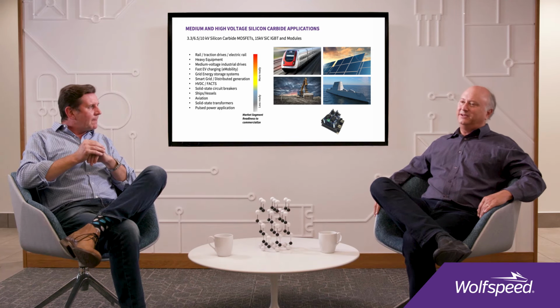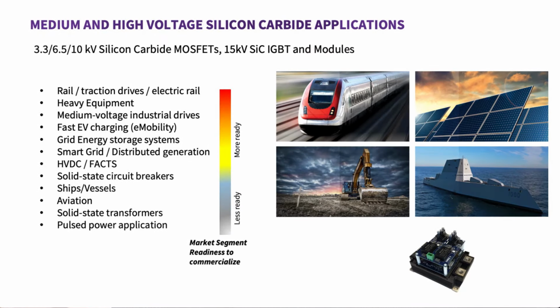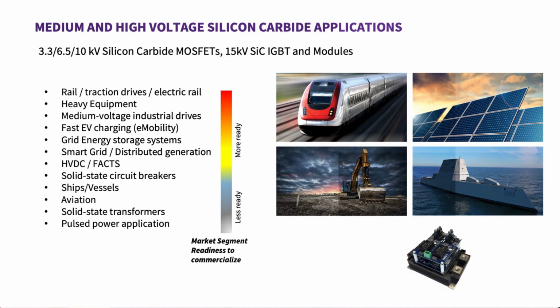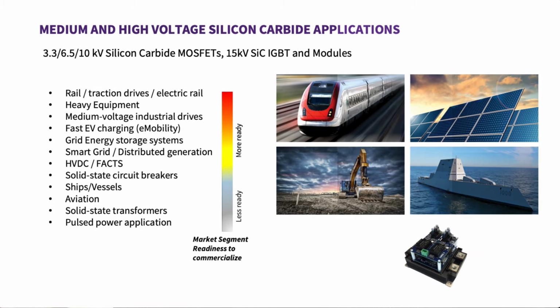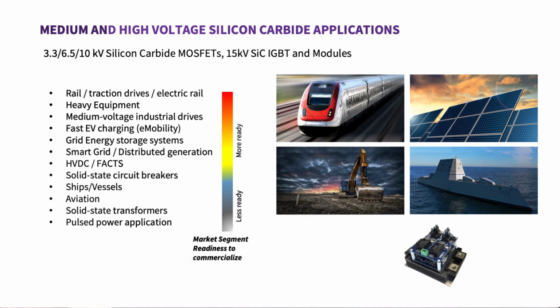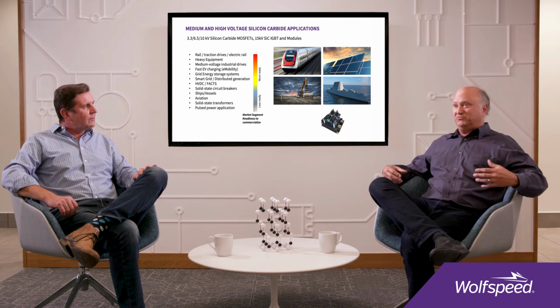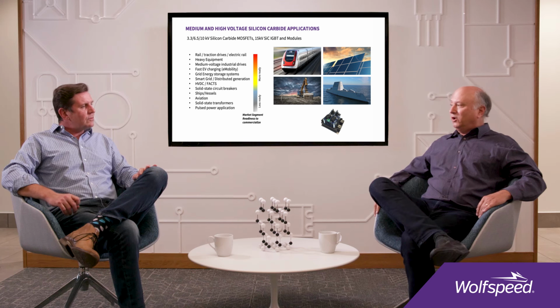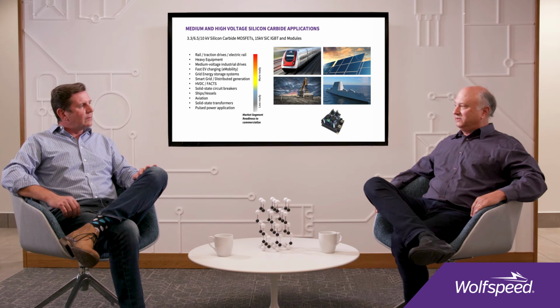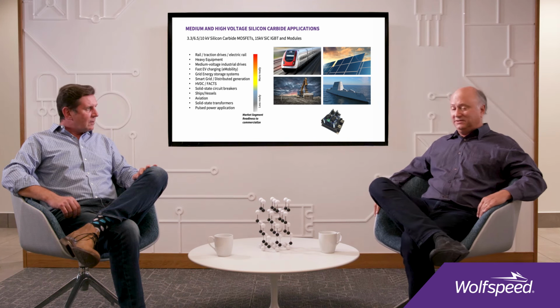But in the case of silicon carbide, we can do a unipolar device, a MOSFET, up to 10 kilovolts. Whereas silicon typically stops around 650 volts. If you want to go to a bipolar architecture like an IGBT, we've demonstrated devices as high as 27 kilovolts - the highest solid state switch ever shown. So it's a whole different realm than silicon plays in today. Different league - completely different league.